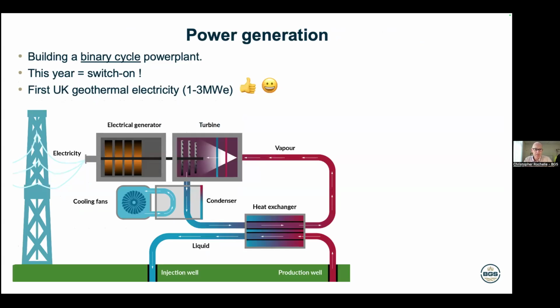In terms of power generation, it's a binary cycle power plant, which basically means there's two fluids involved. If you look at the diagram at the bottom right, the production well produces the hot water, goes to a heat exchanger, and goes straight back underground. The heat is captured in the heat exchanger by a second fluid. In this case, it's pentane, which boils at a lower temperature than water, and it's boiled off into vapor, which turns the turbine and powers the generator.